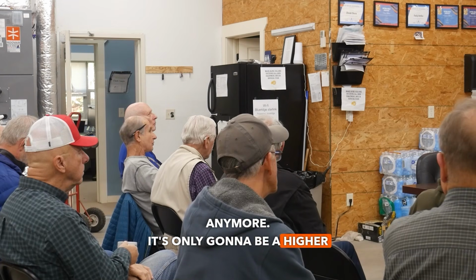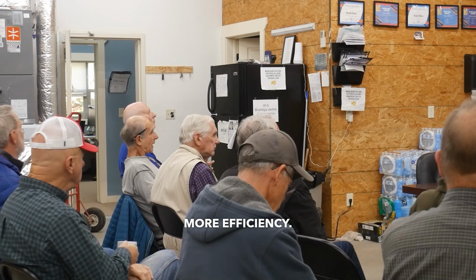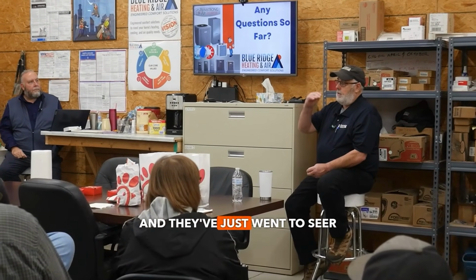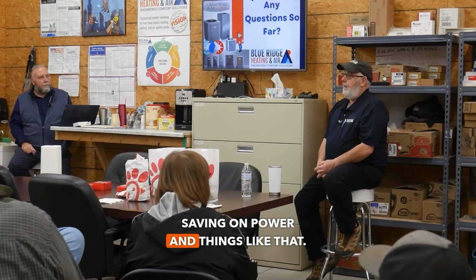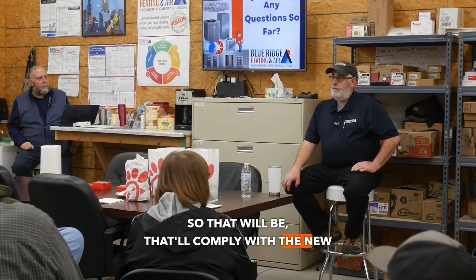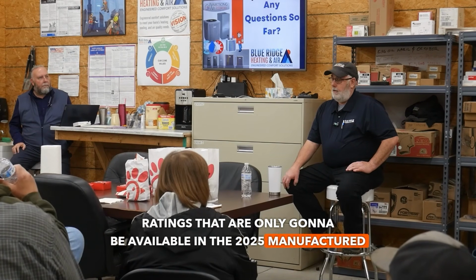It's only going to be a higher SEER rating, meaning higher components, more efficiency. And can you comment on that? Yes, it's a SEER 2 rating. They've changed it from a SEER and they just went to SEER 2. So everything is geared toward being more efficient, saving on power and things like that. I think 14.4 is the minimum you can go, and that's a SEER 2 rating. So that'll comply with the new ratings that are only going to be available in the 2025 manufactured equipment.